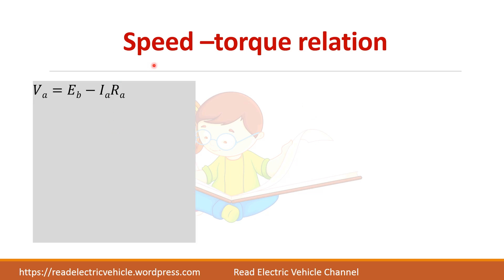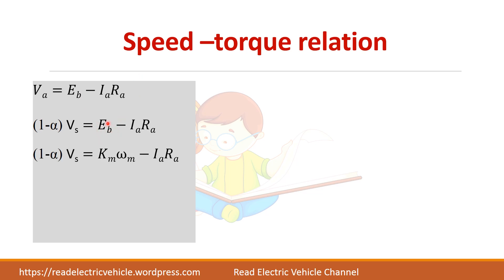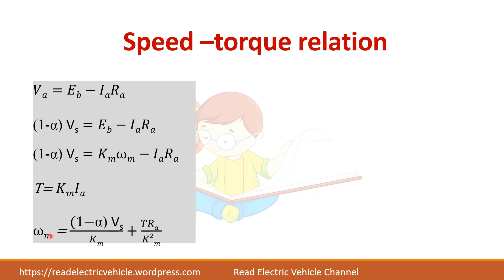Next we will derive the speed-torque relation. For a motor, VA = EB + IA·RA, but here the motor works as a generator, so it is written as EB − IA·RA. The average voltage is (1 − α)·Vs, so (1 − α)·Vs = EB − IA·RA. Since the back EMF EB = KM·ωM, substituting gives ωM. Similarly, torque T = KM·IA, so IA = T/KM, and substituting yields the speed-torque relation.